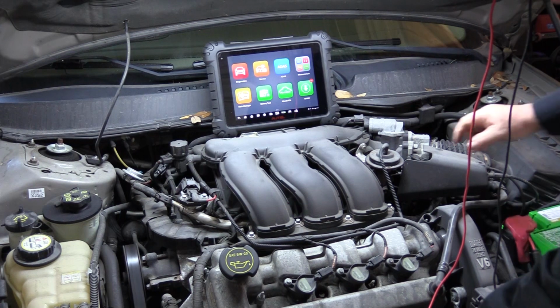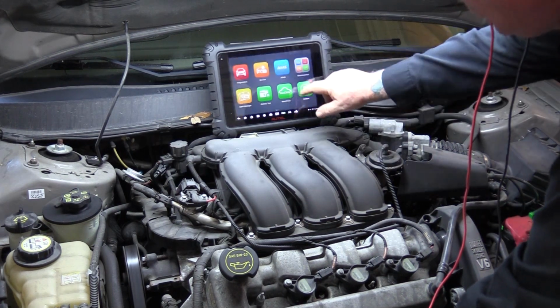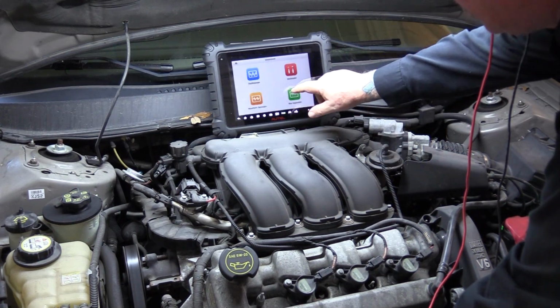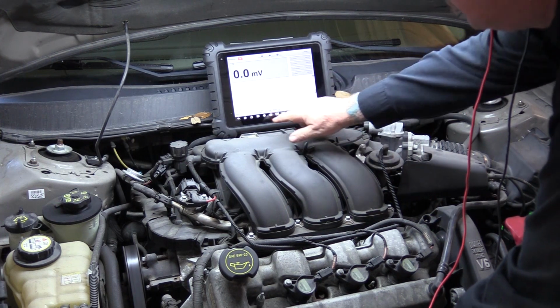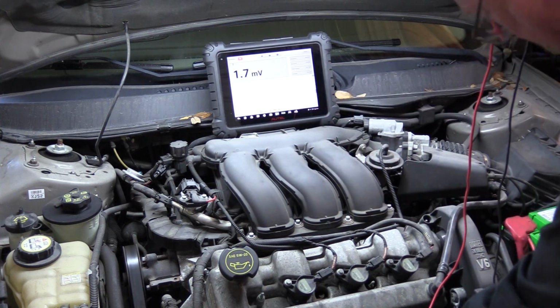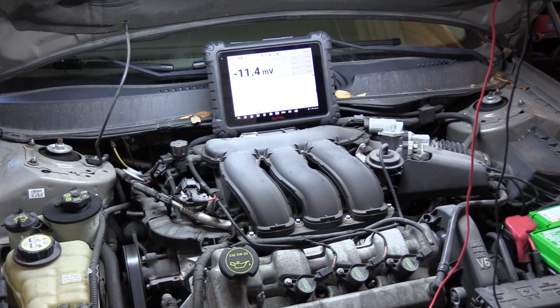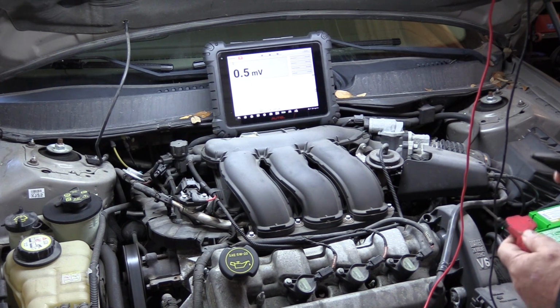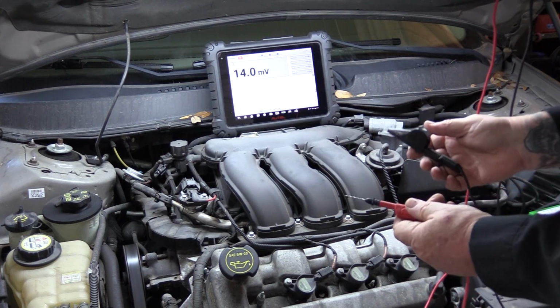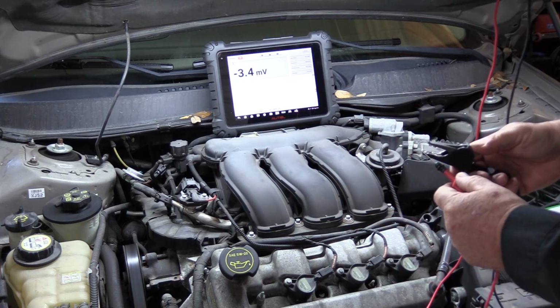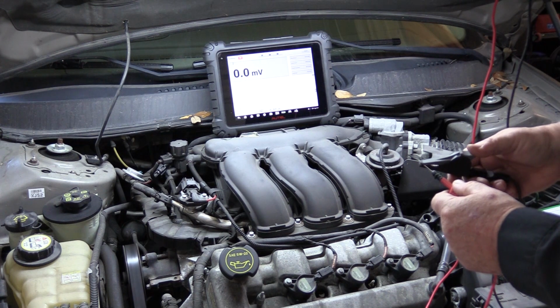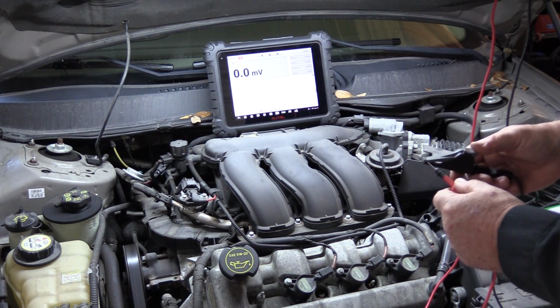So we can also test the system using the multimeter or DVOM function on the MS919. You see it's on DC voltage, our ranging is correct. And again, what you're seeing here is ghost voltage. You see it bouncing around, it means we don't have a good contact. In fact, we're not even connected. If I do touch the leads together, now we have a good connection, no ghost voltage.